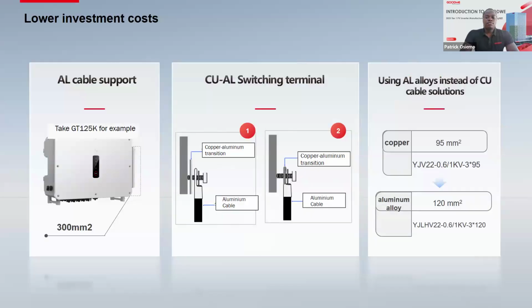Now, if you're focusing on reducing your cost of investments, then the GT series is what you need to install. For example, our GT is able to handle up to 300 square mm size of cable on the input side. And our terminals can offer terminations for both copper and aluminum alloy. So you can do up to 125 per terminal. And yeah, you can also introduce the bimetallic lugs and the likes, and then you will be able to connect aluminum to the terminals of the inverter. So if it's copper, we can do up to 95. If it's aluminum cable, we can do up to 120. And that's the sizing that you can handle to reduce your level of investment.